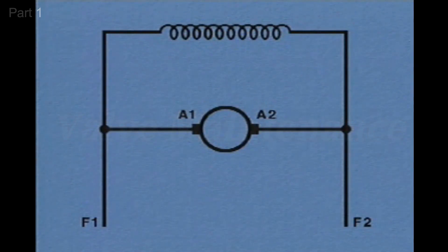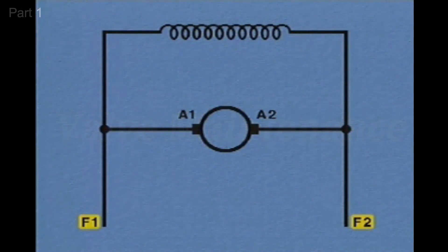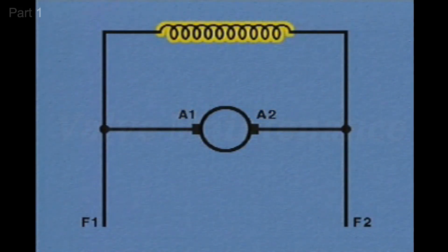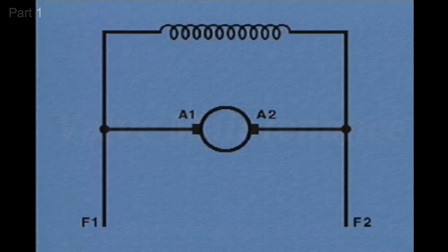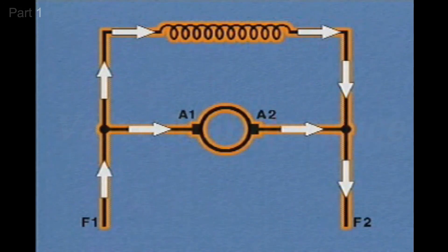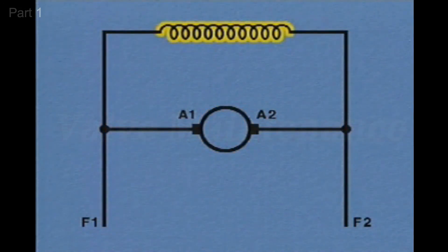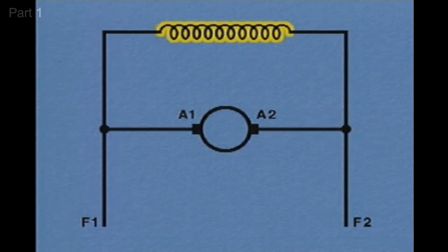This is a schematic of a typical shunt motor. The letter F means shunt, so the shunt field is marked F1 and F2, and the armature is marked A1 and A2. In a shunt motor, the field coils and the armature are always connected in parallel with each other, so there are two paths for current flow. Each coil in a shunt field is usually made of many turns of fine wire, so the resistance in the shunt field is very high.